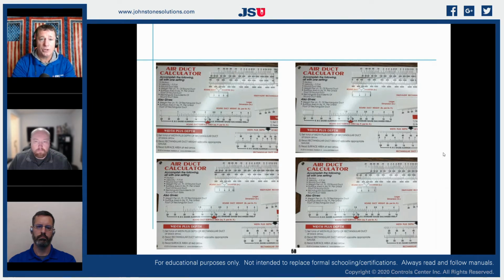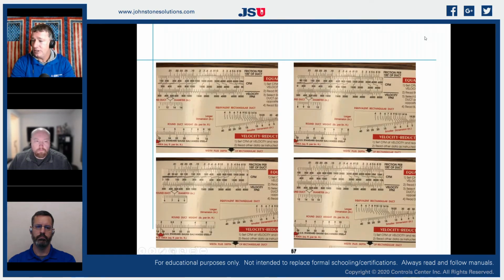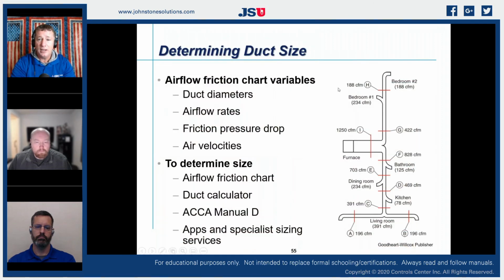So now we've got our first drop, and we've got our transition ready to roll to the next section of ductwork. So we supplied enough air. We took our 8x12 and we ran it past our first drop. We ran all the way to here. And now all that we need is to be able to move 188 CFM to bedroom 2.